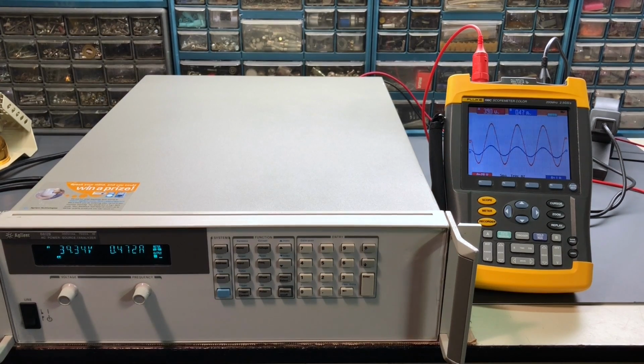Looks like it's about to stabilize there, 0.47, so just slightly under that 1/2 amp. So it seems like the constant current setting is just a little under the entered value. That might be a calibration issue, but it's not too far off. So it looks like that function is working reasonably well.